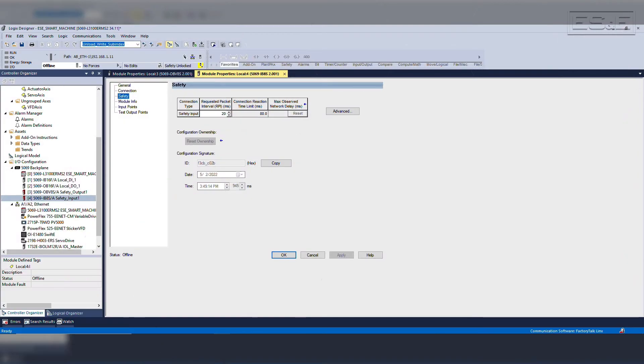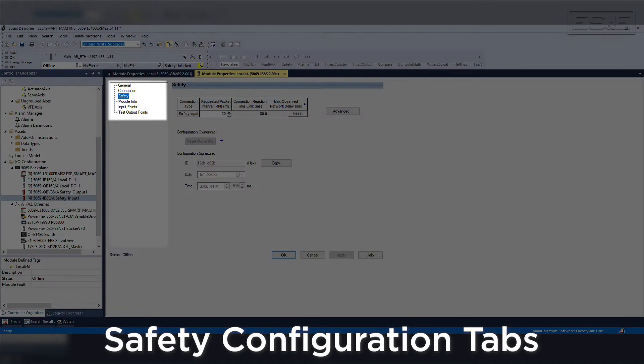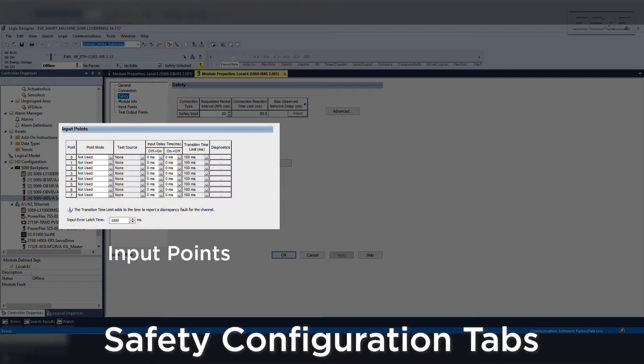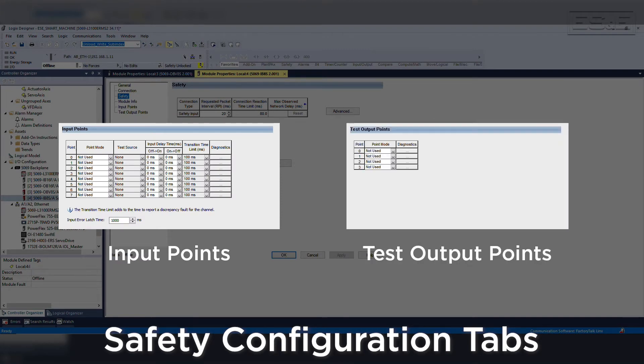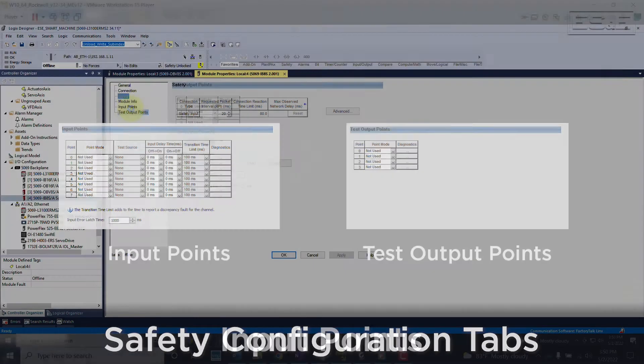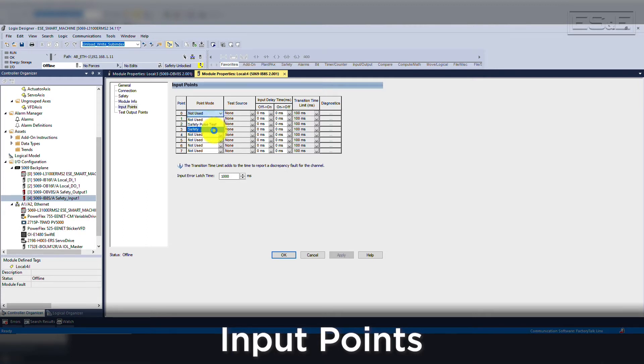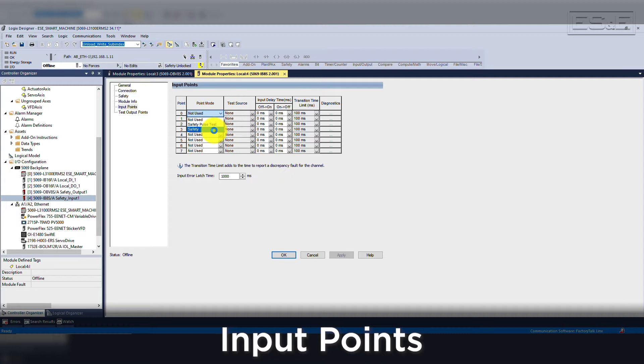In addition to the safety configuration tab, there are more tabs necessary when setting up safety input and output cards. For input cards, you will also have input points and test output points. On input points, you will need to configure if the point is safety or safety with pulse test. Safety is used when the device is an OSSD and has its own pulse testing, whereas safety with pulse test is typically used for contact devices that then need to be monitored by the PLC.